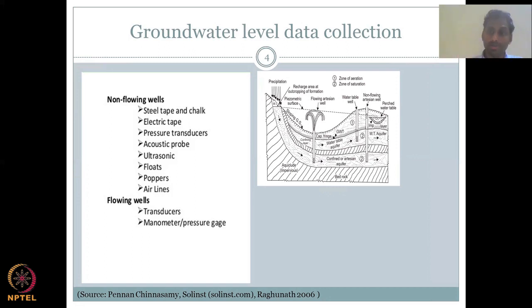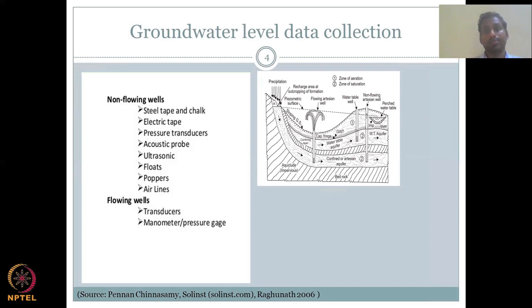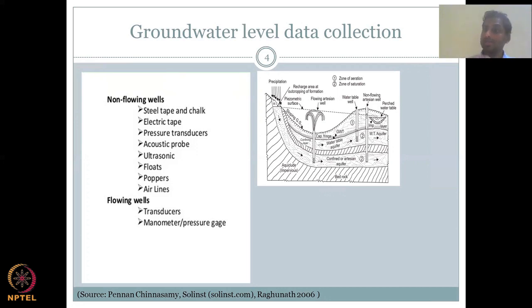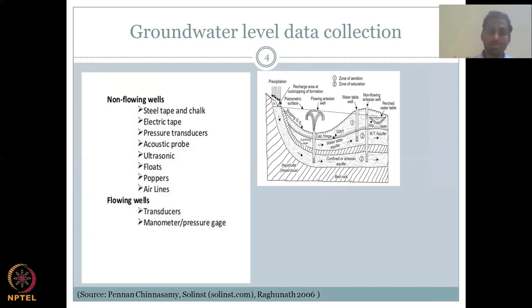A pressure transducer records the pressure difference due to the height of water — when the water level changes, it records the change in pressure. It is a very sensitive instrument that can capture even small changes in groundwater level, and while it is one of the best methods, it is somewhat expensive. Acoustic or ultrasonic probes use sound wave properties to determine water levels from within the well.